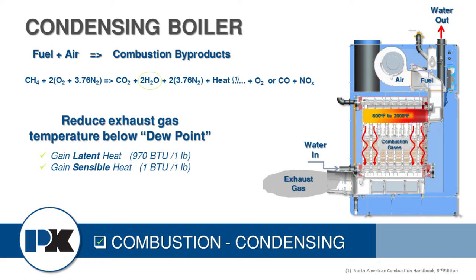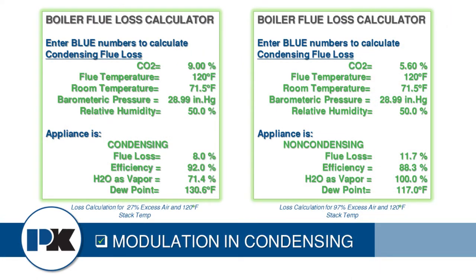Looking at a picture of the condensing boiler: the flame is at the top, combustion gases go down through the heat exchanger, and water goes up through the heat exchanger. What we want is for the combustion gas to be cooled by the heat exchanger water so that by the time it reaches the bottom before exiting, it's dropped below the dew point. This is why we want to keep that dew point as high as possible.